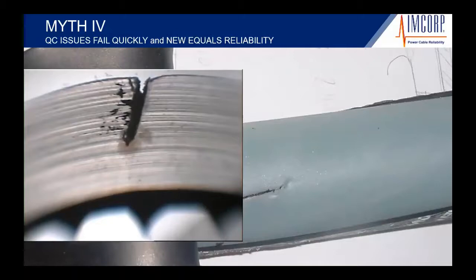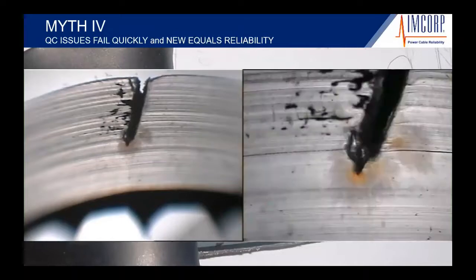This is the utility application, so this is 90 degrees C cable, really operates about 40 degrees C. The load is not very heavy on it. So we think because of the size of the gash, or the cut, and the application, this particular cable never went to failure, but we did take it with some over voltage. We were able to find that it was discharging and it had carbon trees that were developing. A closer look at it, you can see some of the water trees that have been developed. We know that it takes decades for water trees to show up, so we know this is an old cable.